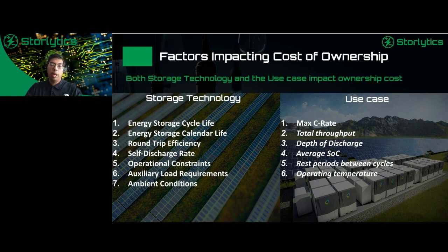So if I go into the storage technology, you've got to look at the cycle life and calendar life of the battery - that directly impacts your initial oversize factor, or how many augmentation cycles you will need, which has an impact on your overall cost. Then you have your round trip efficiency and self-discharge, which impact your overall energy loss.